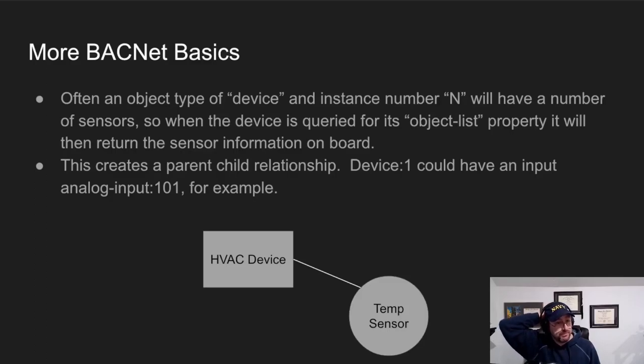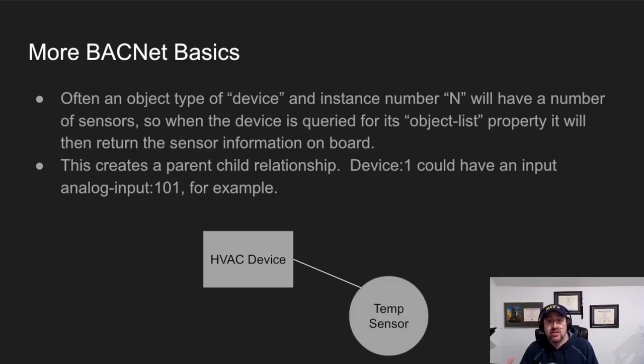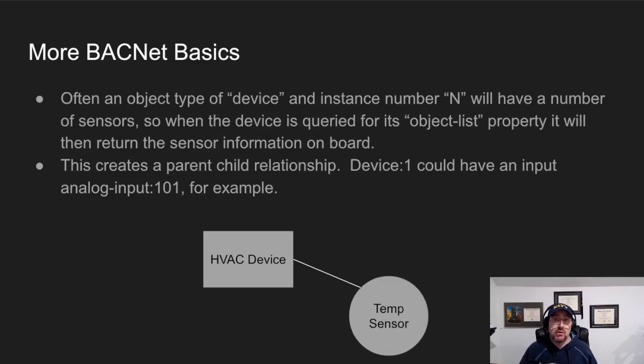Most times an object will have an object type of device, meaning a physical device as a human would think of it. Every BACnet object has an instance number on the network. An HVAC device that you put on your network might have 16 sensors in it, and each of those 16 sensors will look like other BACnet objects on your network, which makes things confusing in terms of how devices relate to each other.